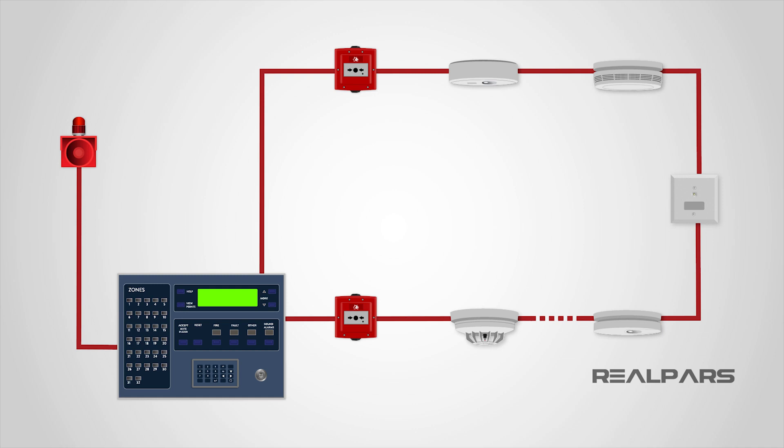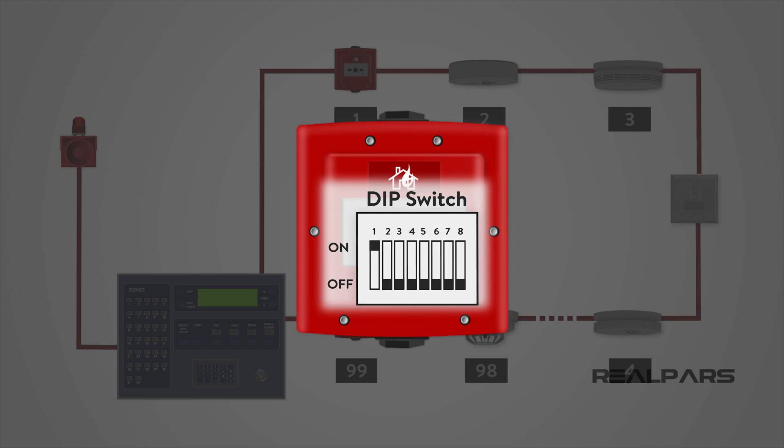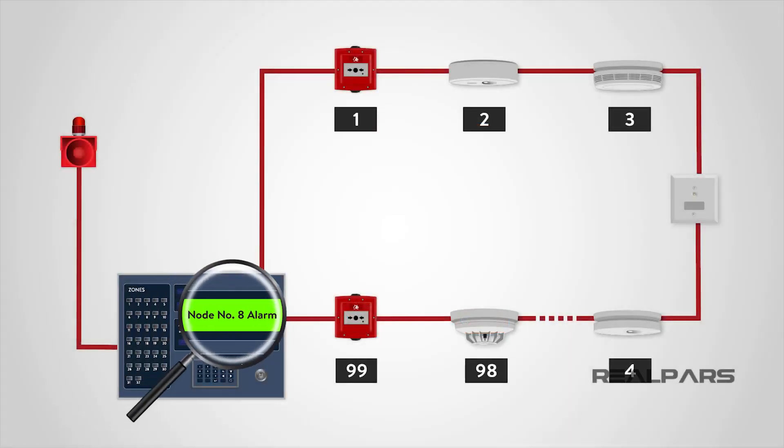The detection principle of an addressable system is the same as a conventional system, except that each detector is given a set address, usually by means of a dip switch, and the control panel can then determine exactly which detector or call point has initiated the alarm.